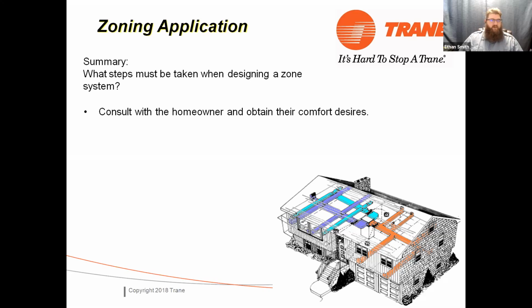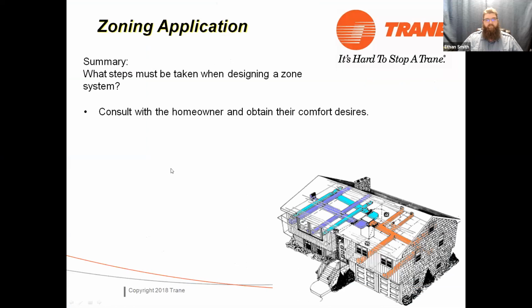Okay. What would you guys say is the next most important thing? Your square footage for each zone. Okay. For CFMs. Separating out your zones, your CFM, what goes along with that? You got to know your load, right? Okay. You got to make sure that your CFM is going to match your load for each zone. So doing your research on your ductwork, your load, what else? What comes after that? How well the house is insulated. Okay, that's going to factor into your load for sure.